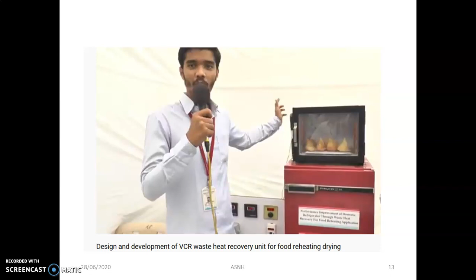So the design, mechanism and fabrication process. Develop a separate rectangular hot box to keep on the refrigerator, surrounded with thermocol, thereby making a panel side to fit the voltmeter, ammeter, temperature indicator, HP and LP cutoff, and energy meter. Two pressure gauges are used. In order to calculate the coefficient of performance, we need the condenser and evaporator pressure. Also we need the LP and HP cutoff and energy meter in order to find out that COP.